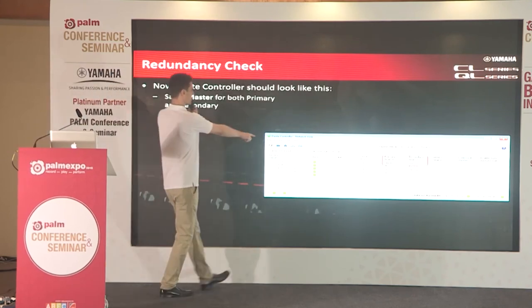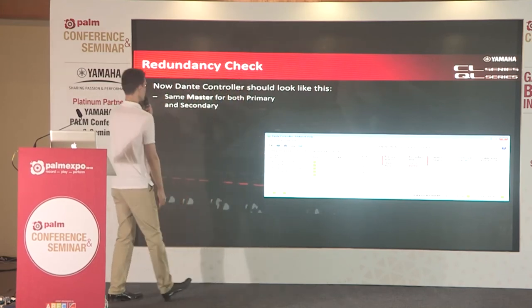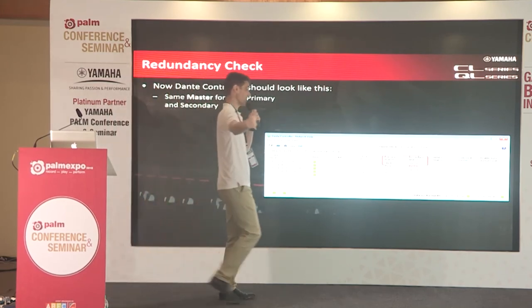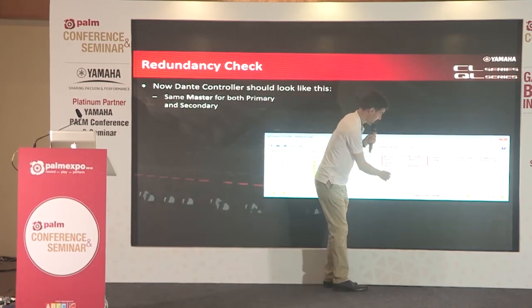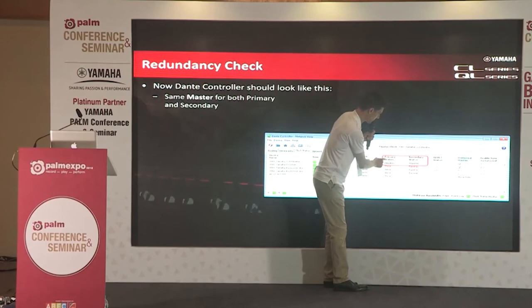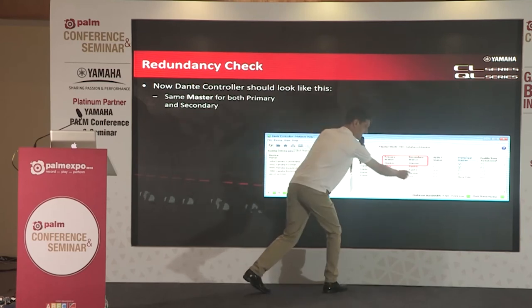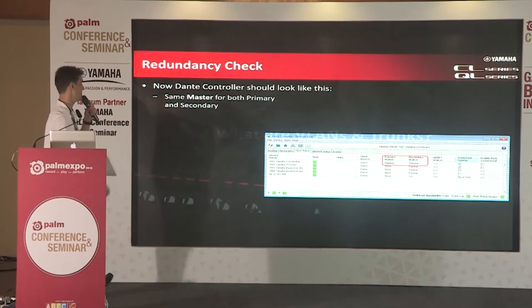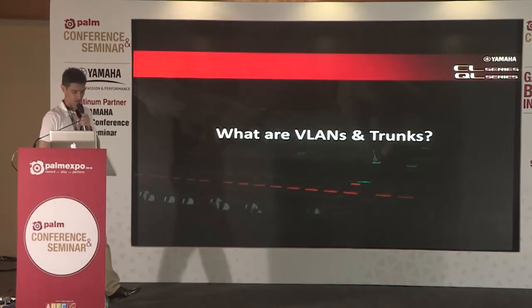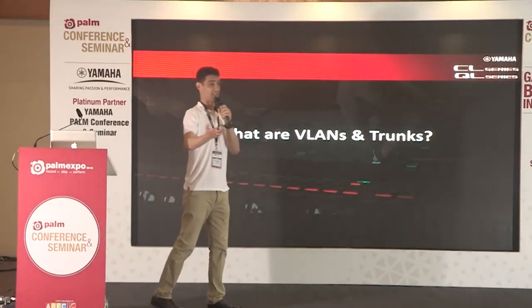Go back to your clock status page and check your network master. If your network is built correctly, you'll have the same master for both primary and secondary networks. If there are different masters, you know there's a problem somewhere, and you can then check your cables and connections.